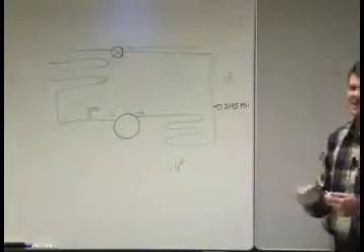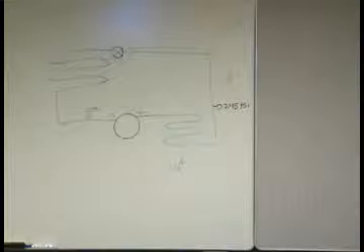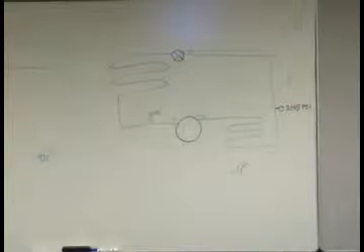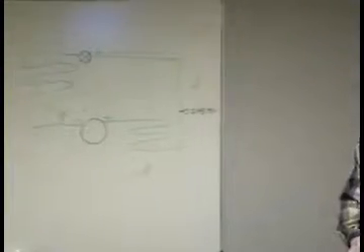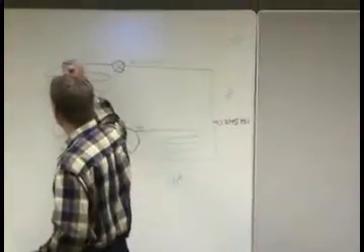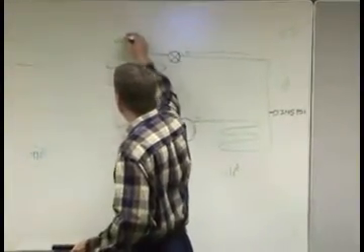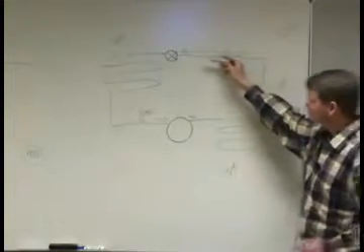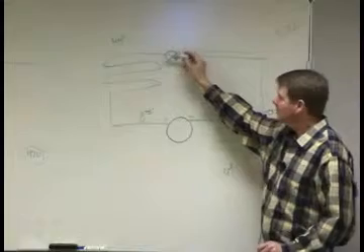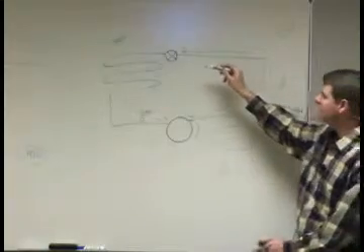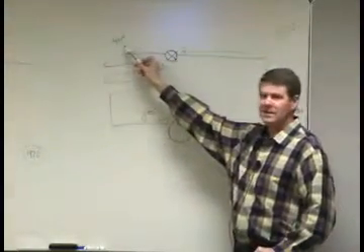So at 75 psi, what's my boiling point of my R22? 133. Can't be. 44. 44? So this thing over here now is going to boil at 44 degrees. So we got this liquid coming in. All of a sudden, on the other side of this, it's dropped down to 75 pounds. So now its boiling point has just been dropped to 44 degrees.